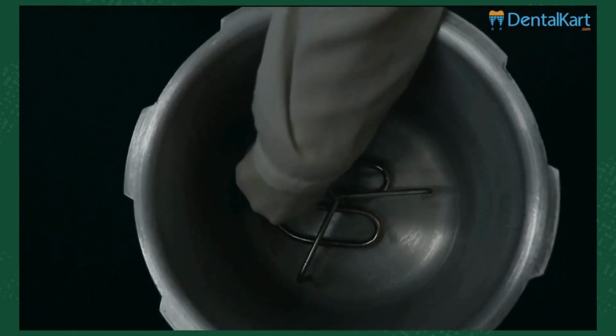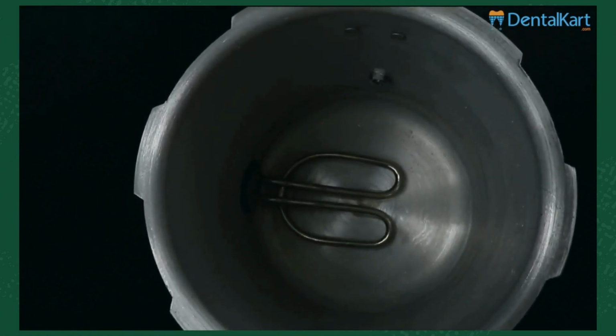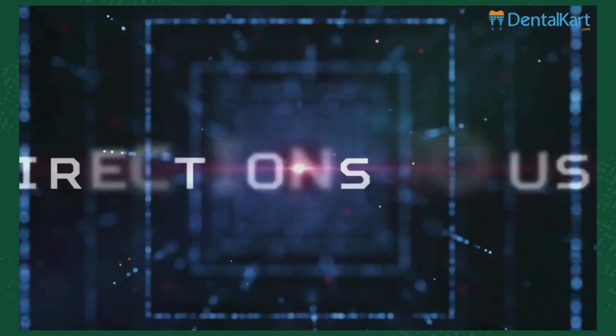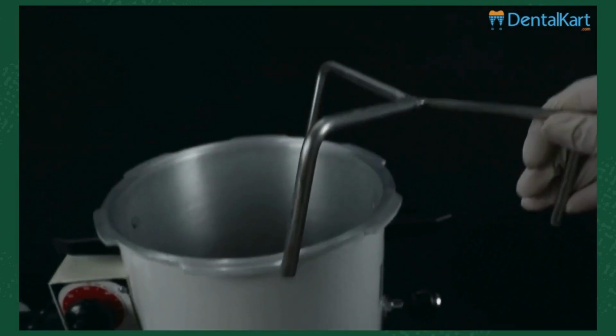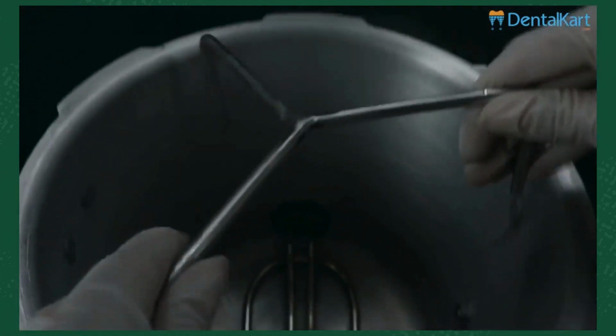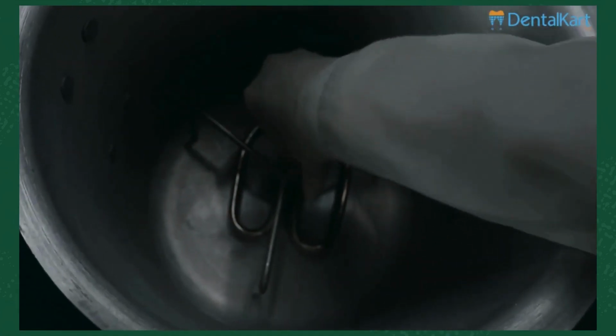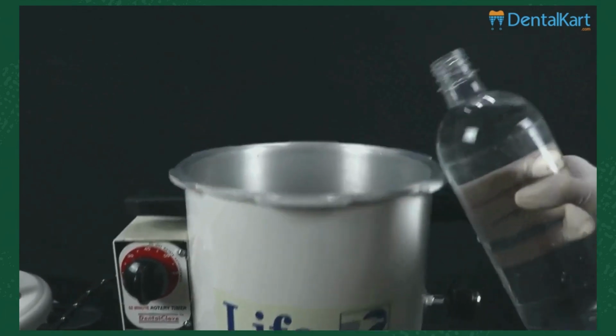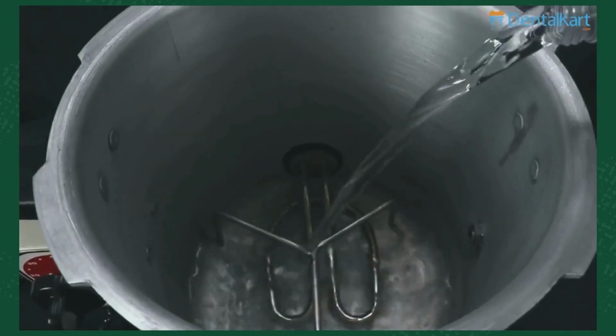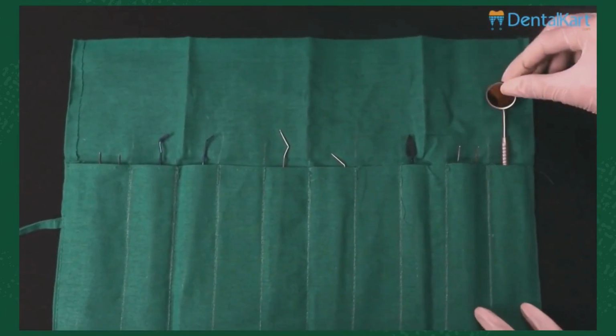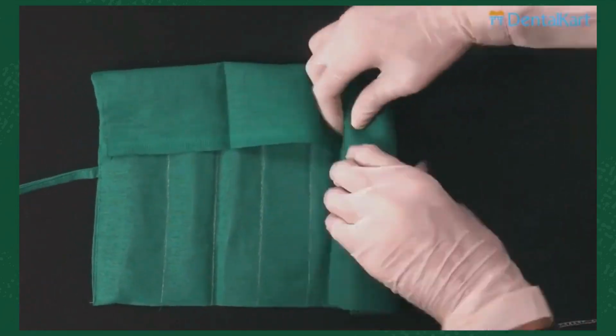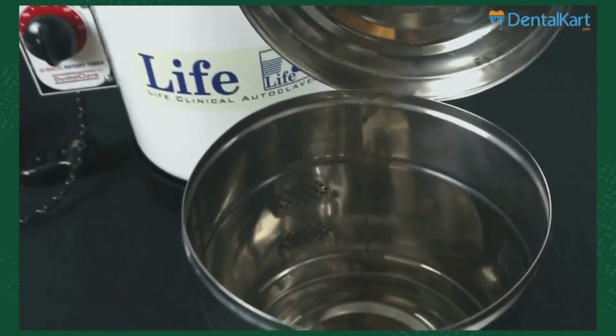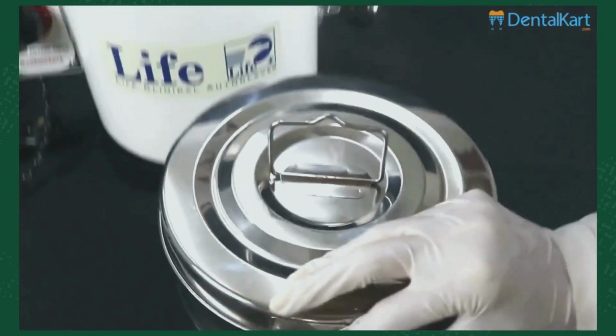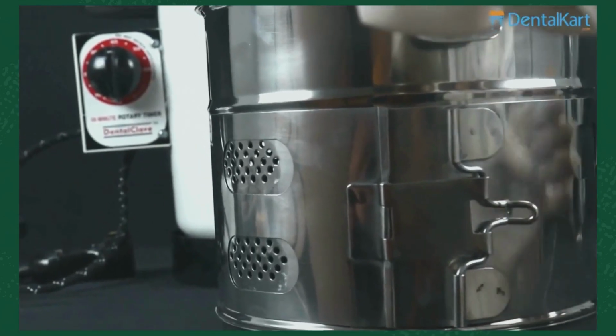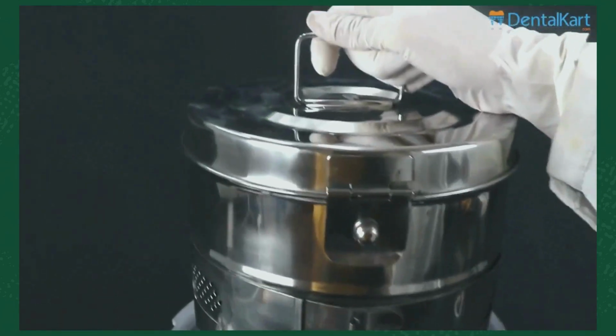Inside the autoclave, there is a stand for the stainless steel drum and the heating element. First, place the stand inside the chamber. Now submerge the chamber with distilled water. Then keep the instrument inside the green cloth and then place the green cloth inside the drum. And place it inside the autoclave chamber.